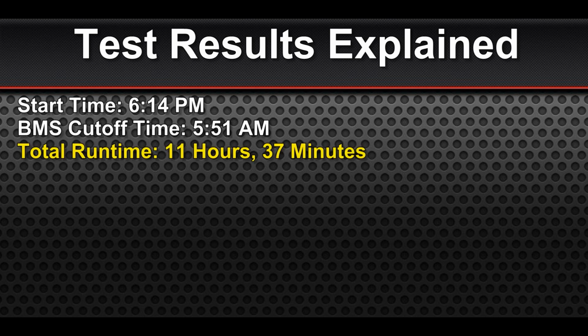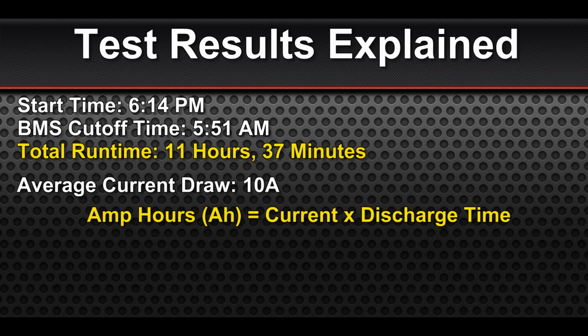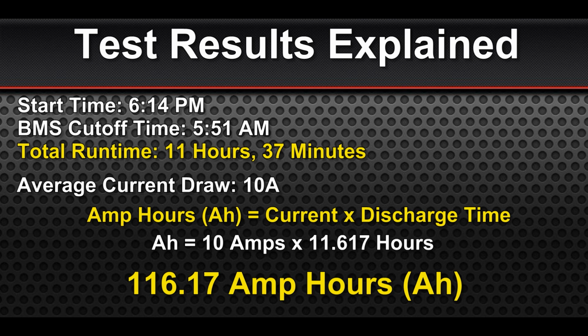Let's look at the test results. We had a start time of 6:14 p.m. and a BMS voltage cutoff at 5:51 a.m., for a total run time of 11 hours 37 minutes. Average current draw during the test was 10 amps. Using the formula shown, we calculate amp hours by multiplying current times discharge time. Plugging in our known values of 10 amps and 11.617 hours, our 100 amp hour rated battery gave us 116.17 amp hours before BMS cutoff.